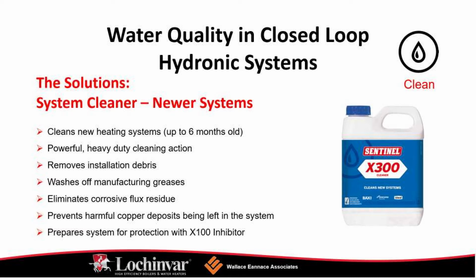So what are we getting at? Lifetime protection for heating and hot water systems is important, and it's only going to be met if you're maintaining best practices. So it's very important to make sure we clean, protect, and maintain our closed loop hydronic systems. And as mentioned just a few seconds ago, using a product like Sentinel is certainly one way to do it.